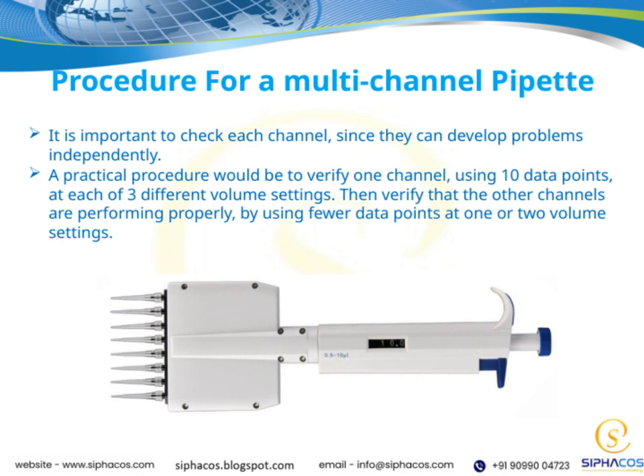Once you've confirmed that one channel is working properly, you can then verify the other channels. For these, you don't need as many data points, fewer will do, and you can focus on just 1 or 2 volume settings. It's really important to check each channel individually because they can develop problems independently of each other. If one channel is off, it won't necessarily affect the others, so thorough testing helps catch issues early and ensures accuracy and reliability across all channels. Overall, this step-by-step verification process helps maintain precision and confidence in your pipetting, which is essential for high-quality results in your work.